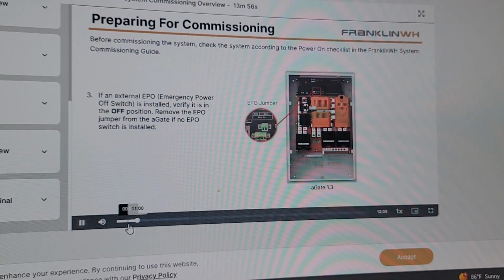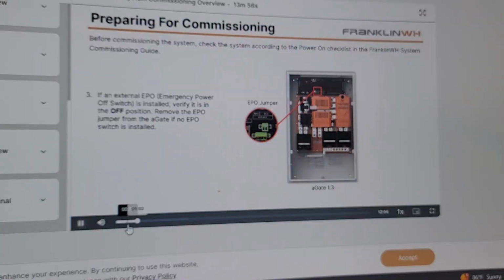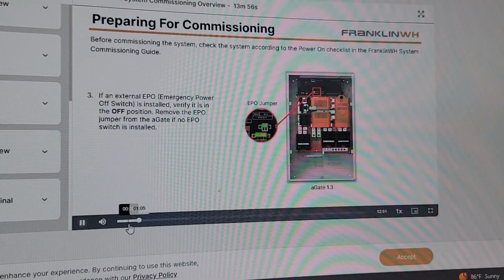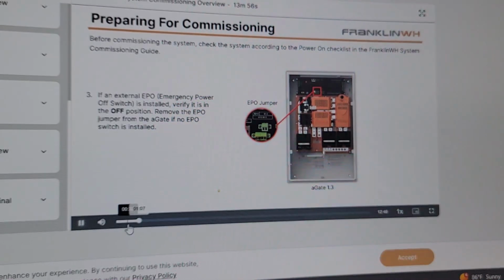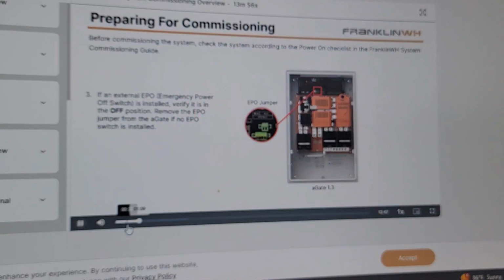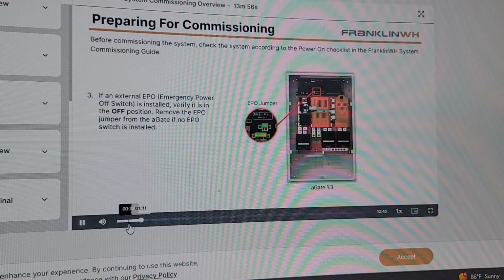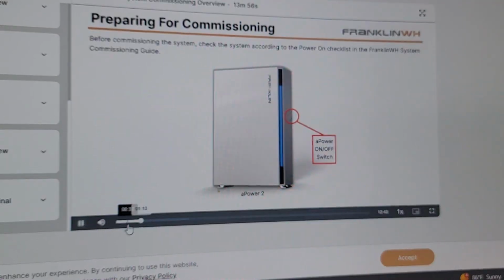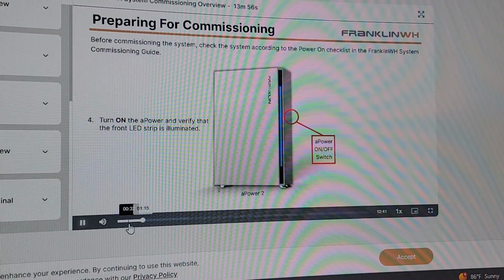Step 3. If an external EPO, emergency power off switch, is installed, verify it is in the off position. Remove the EPO jumper from the aGate if no EPO switch is installed. Step 4. Turn on the aPower and verify that the front LED strip is illuminated.